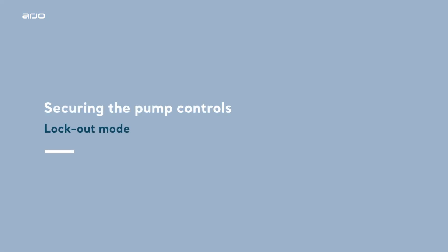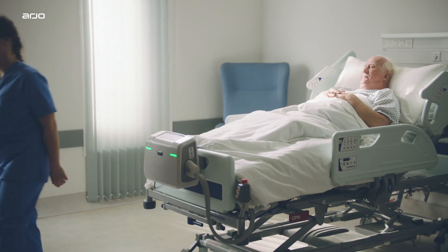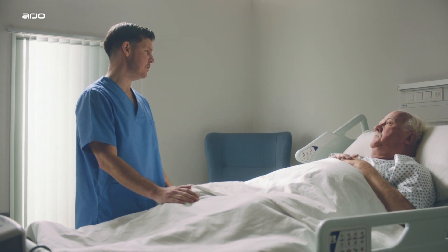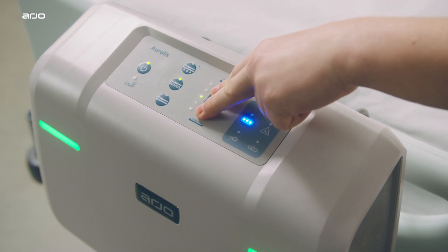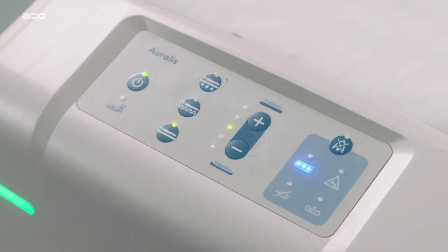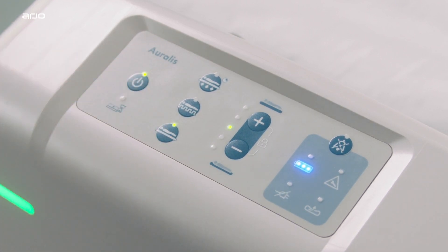Securing the pump controls: lockout mode. Auralis is available with a lockout feature which, when enabled, locks the pump control interface from operation, supporting peace of mind for the caregiver. This is specifically designed to help minimize accidental or unauthorized operation of the pump. Lockout is activated or deactivated by pressing and holding the comfort control buttons simultaneously for at least two seconds. When the pump is in lockout mode, pushing any button will result in a negative tone and the top and bottom comfort control indicators flashing simultaneously.